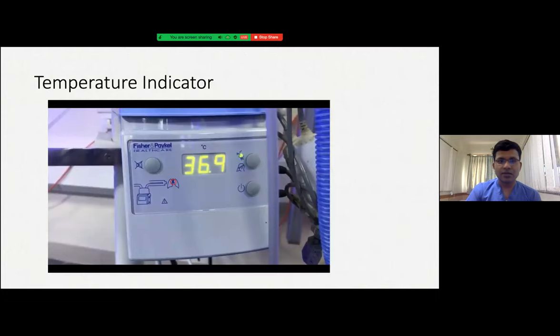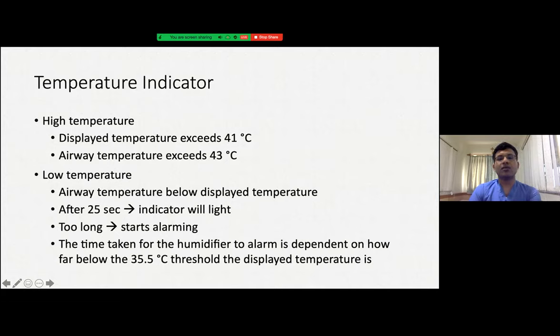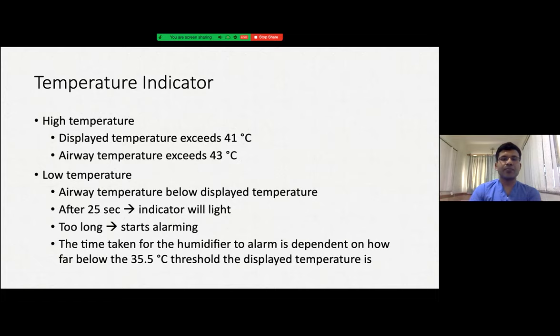Sometimes a temperature alarm occurs inside the airway due to very high or very low temperature. High temperature is usually indicated when it is more than 41 degrees and starts alarming when it is more than 43 degrees, which can be dangerously high and damaging to the patient. For low temperature, if it is below the set temperature for 25 seconds, the light starts blinking; if too long, it starts alarming. The time to alarm depends on the threshold — a 6-degree difference will trigger alarming earlier, while a 1 to 2 degree difference takes longer. Thank you.